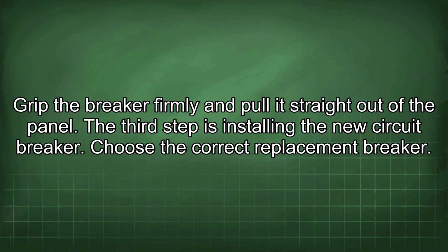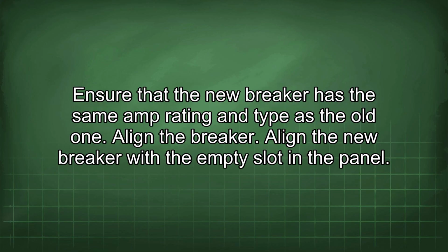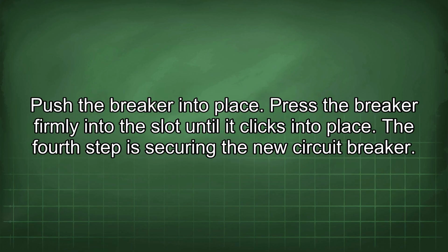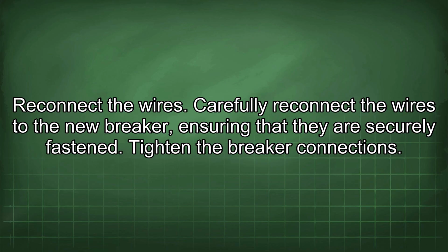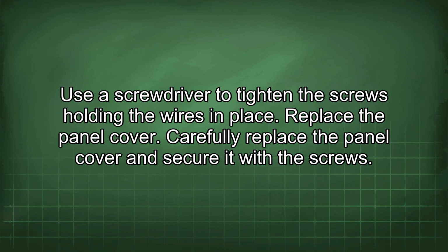The third step is installing the new circuit breaker. Choose the correct replacement breaker. Ensure that the new breaker has the same amp rating and type as the old one. Align the breaker. Align the new breaker with the empty slot in the panel. Push the breaker into place. Press the breaker firmly into the slot until it clicks into place. The fourth step is securing the new circuit breaker. Reconnect the wires. Carefully reconnect the wires to the new breaker, ensuring that they are securely fastened. Tighten the breaker connections. Use a screwdriver to tighten the screws holding the wires in place. Replace the panel cover. Carefully replace the panel cover and secure it with the screws.